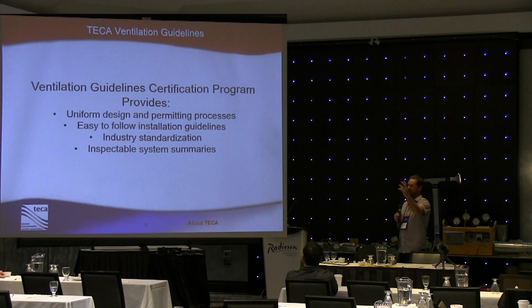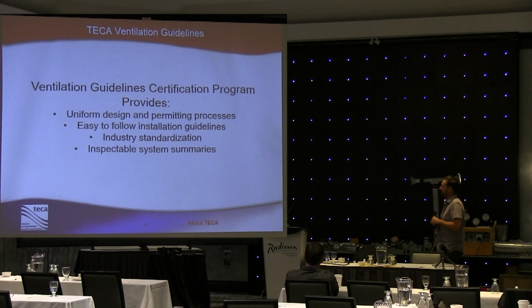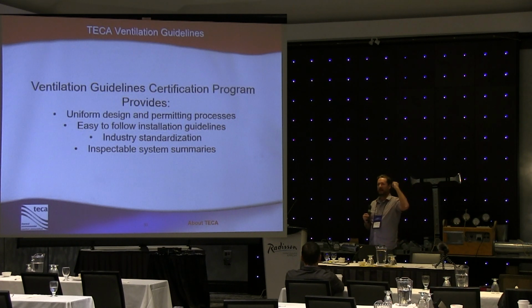That worksheet, in turn, that the contractor turns in to the municipal authority, the AHJ, should become your inspection worksheet. That should be on site when you're doing your building final walkthrough before drywall or before installation, whenever your municipality says that you need to be looking at that. That worksheet should be your guideline. You should be able to go through and confirm that the fans are installed, that the ductwork is sized correctly, and that the contractor actually has a clue of what he or she is doing.